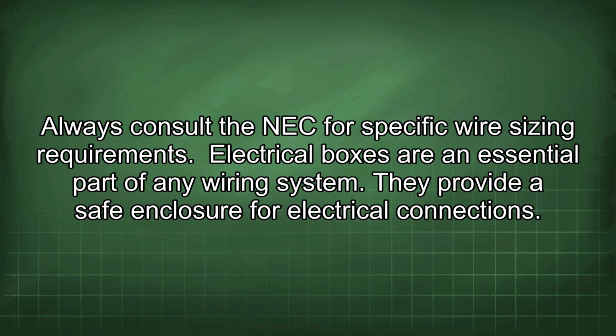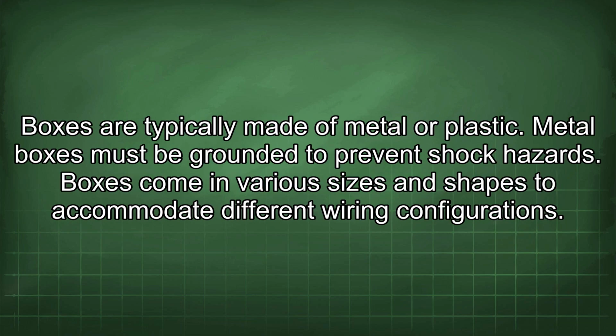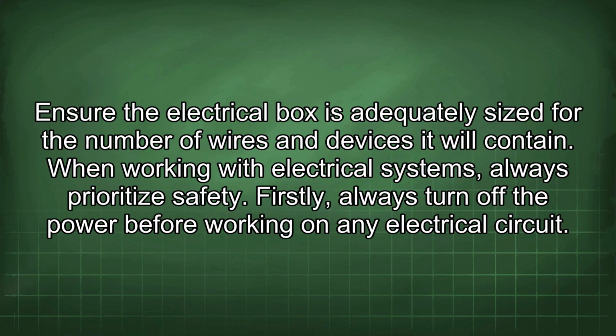Electrical boxes are an essential part of any wiring system. They provide a safe enclosure for electrical connections. Boxes are typically made of metal or plastic. Metal boxes must be grounded to prevent shock hazards. Boxes come in various sizes and shapes to accommodate different wiring configurations. Ensure the electrical box is adequately sized for the number of wires and devices it will contain.